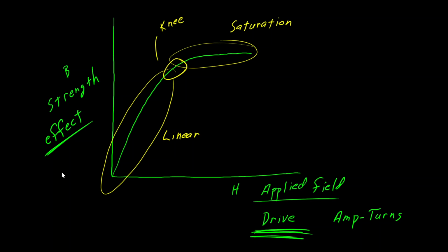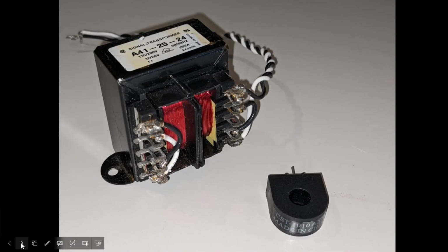As you'll see in a moment, once the drive passes the knee, the input current will increase at a very rapid rate. In fact, applying more voltage on a winding than it's rated for is a very quick way to destroy a transformer. Let's do a quick review and then we'll move to the actual testing.